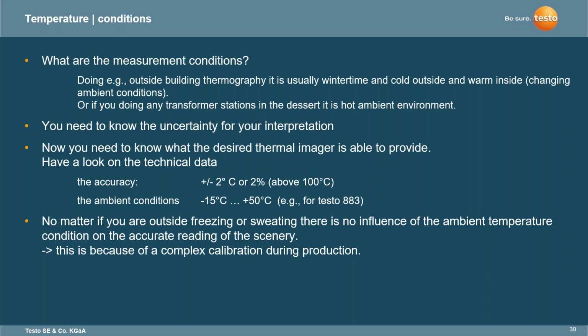But the one thing with Testo is we also take into account the measurement conditions. So are you doing work outside, or inside? We understand that each region is very different. It's cold, it's hot, there are always changing ambient conditions. Or if you're doing transformer stations in the desert, it is a hot ambient environment. You need to know the uncertainty for your interpretation, and you need to know what the desired thermal imager is able to provide, so have a look at the technical data.